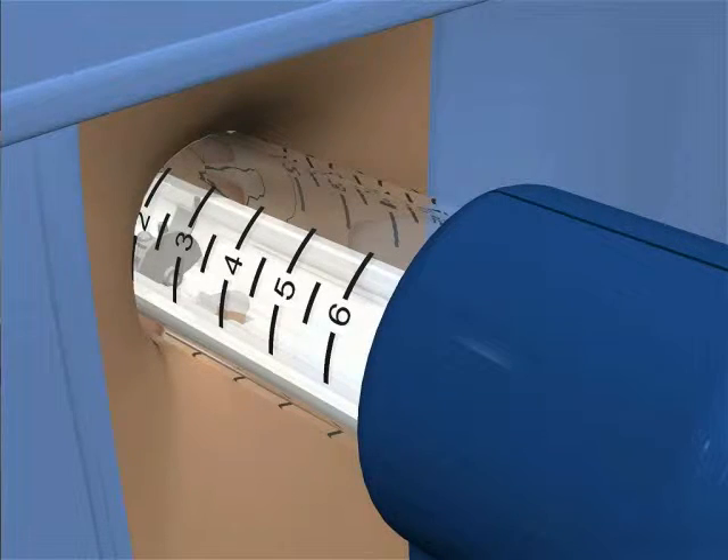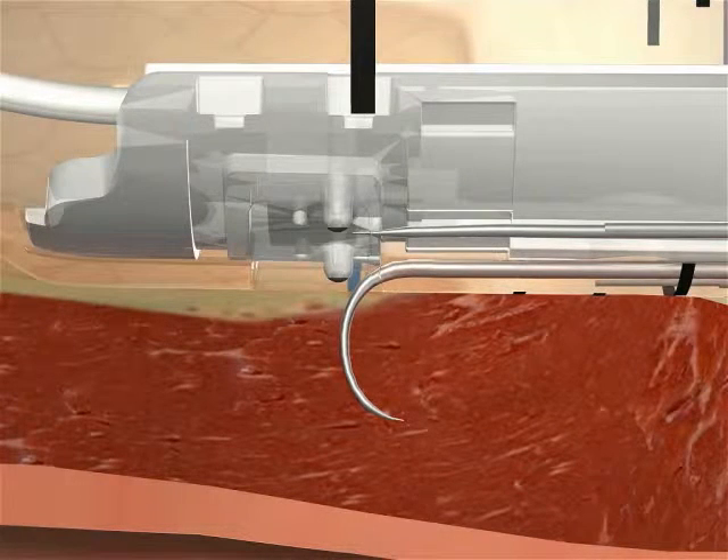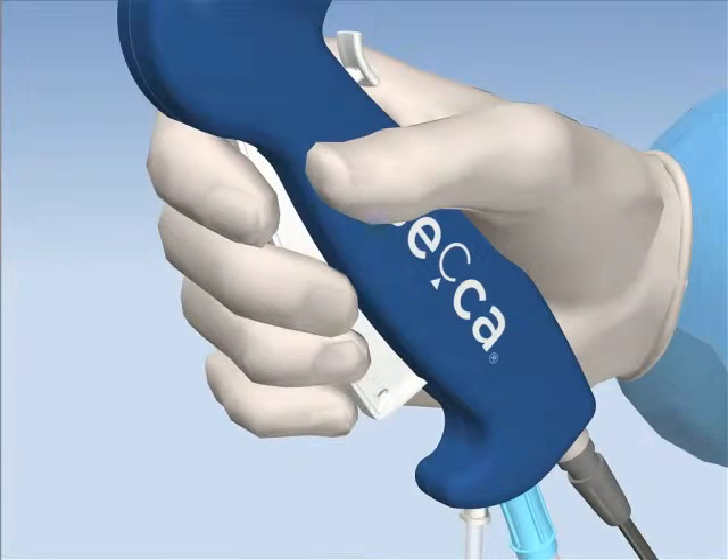Extend the needles. While holding the handpiece firmly against the rectal wall in the proposed treatment quadrant, squeeze the trigger to extend the needles on the Secca handpiece. This will help achieve optimal impedance levels. While applying pressure, squeeze the trigger until an audible click is heard. That signifies that the needles are locked in the extended position. It is not necessary to maintain squeeze pressure on the trigger once the needles are extended and locked.